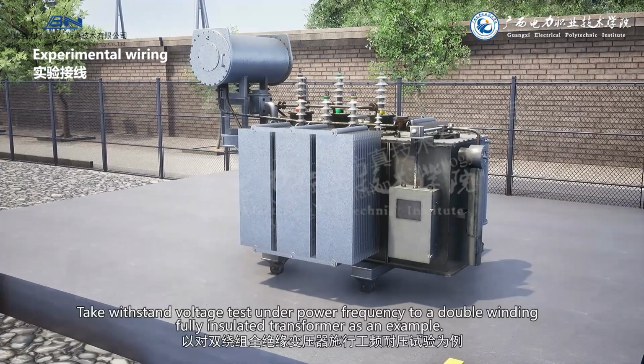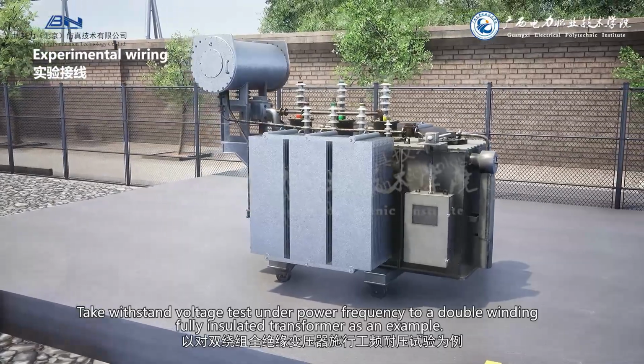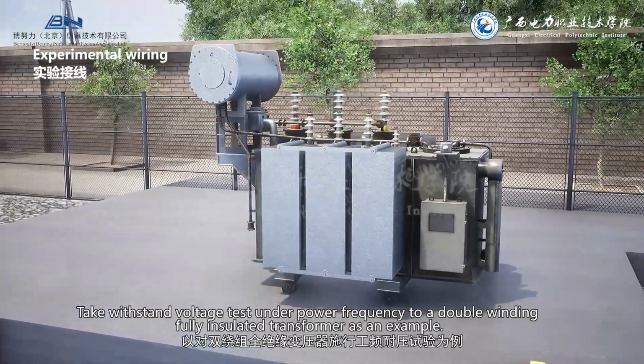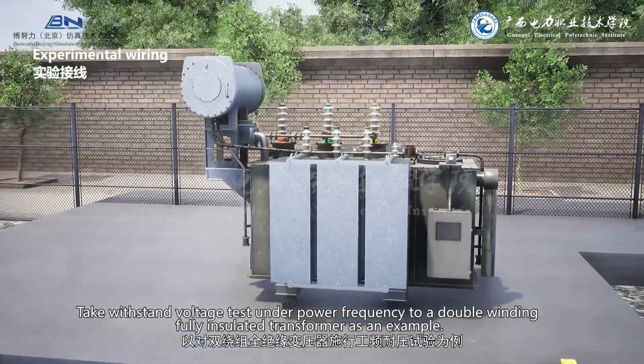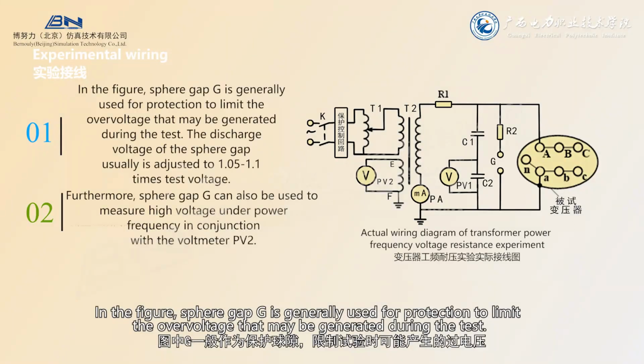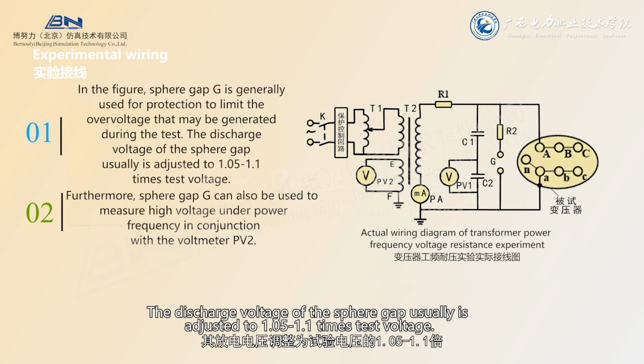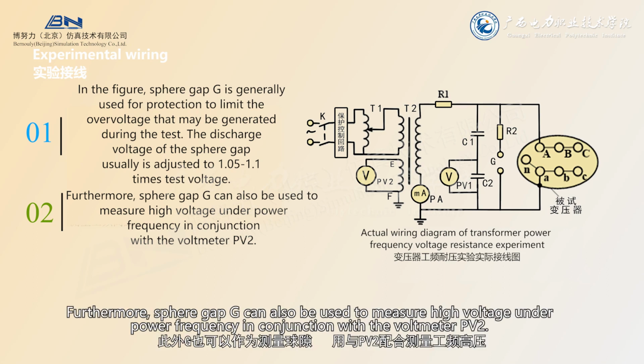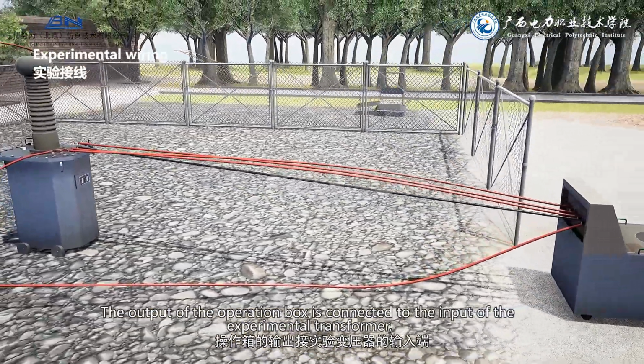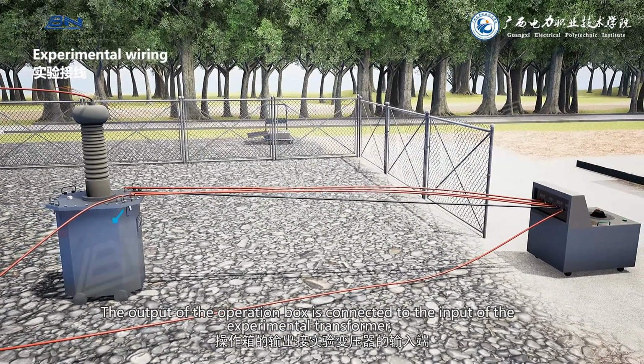Take withstand voltage test under power frequency on a double-winding, fully insulated transformer as an example. The protective ball gap limits the overvoltage that may occur during the test, and its discharge voltage is adjusted to 1.05 to 1.1 times the test voltage. It can also be used as a measuring ball gap to measure the working frequency high voltage in conjunction with the PV2. The output of the operation box is connected to the input of the experimental transformer.